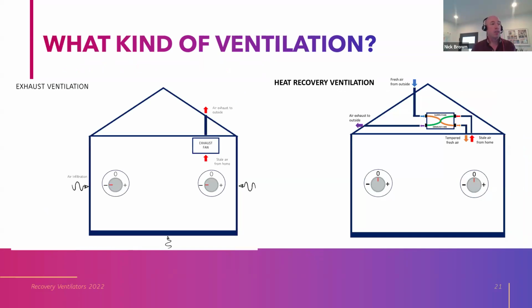So here's an illustration we created to talk about the pressure difference. With exhaust ventilation like shown here, the exhaust fan is mounted somewhere in a ceiling, exhausting to the outside, taking stale air from the home. That creates negative pressure in the space. And that sucks in outside air through tiny holes in the building envelope. I don't care how well you've built this house, you've got tiny holes. So that's the source of your fresh air.